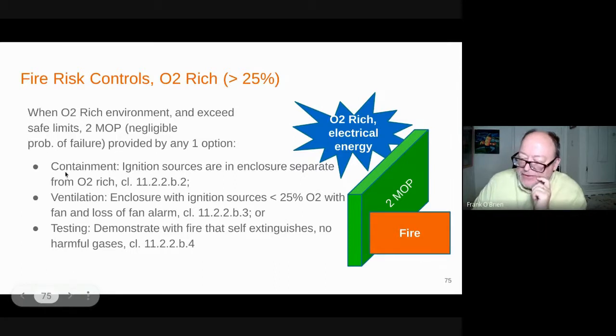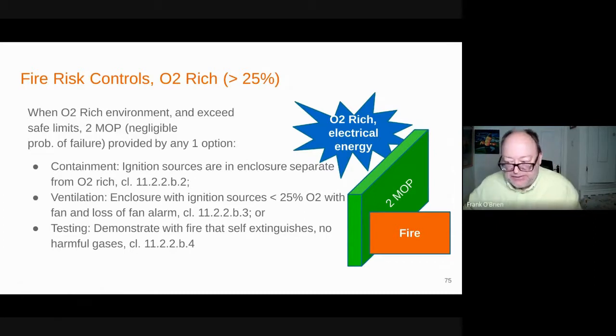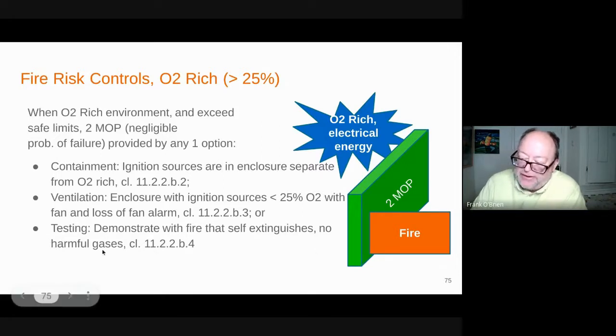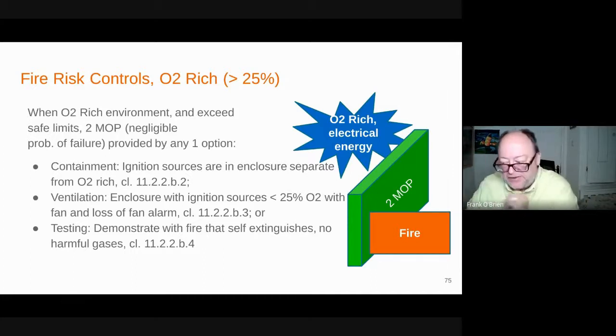But generally, we're going to take one of three approaches because we exceed those energies. And so we have to contain the oxygen away from the energy sources. And we can do that if the oxygen stays within a breathing tube and the electronics is somewhere else. The oxygen might get into the electronics box, but we're going to have ventilation to not allow the concentration to exceed 25%. And we'll have an alarm if the fan should fail. Or we can do testing to demonstrate there's no fire. And so these are the design strategies for everything. But we're still going to have oxygen rich somewhere, but we've kept it away.